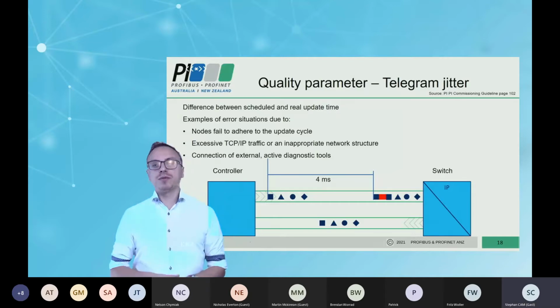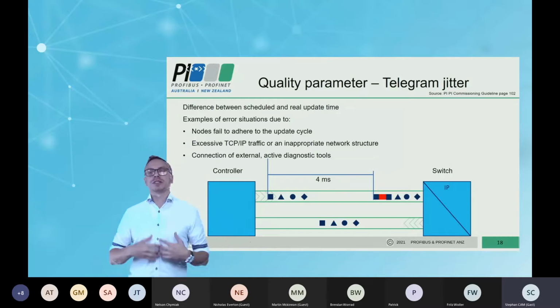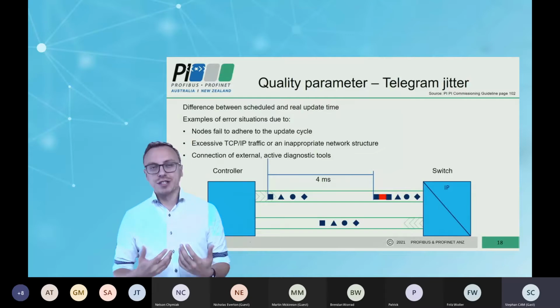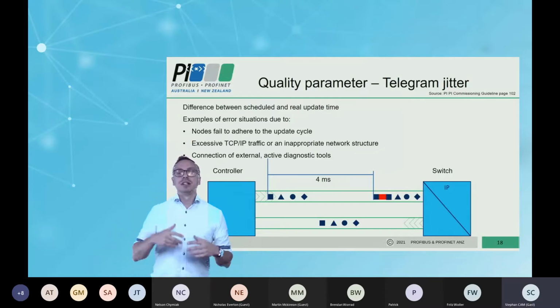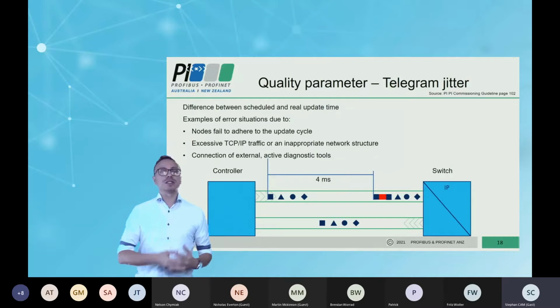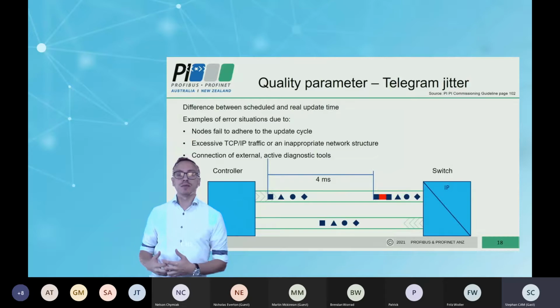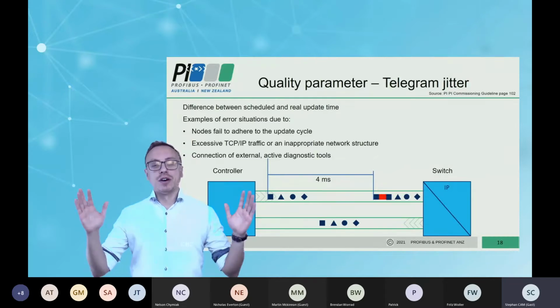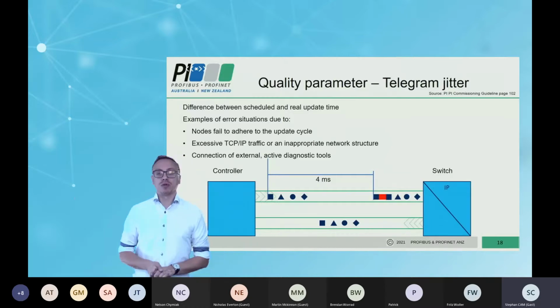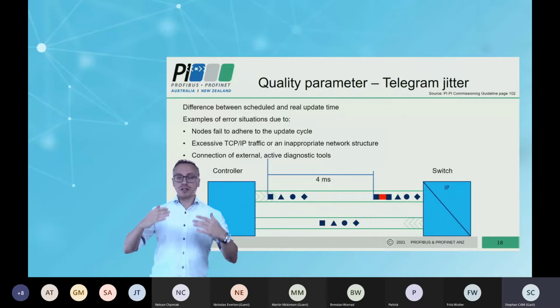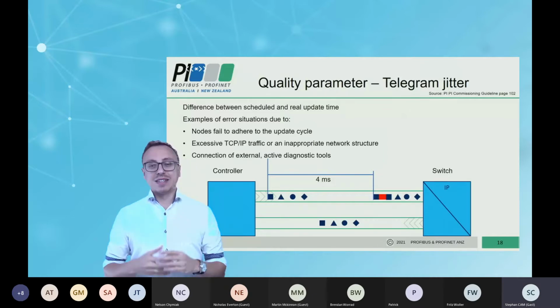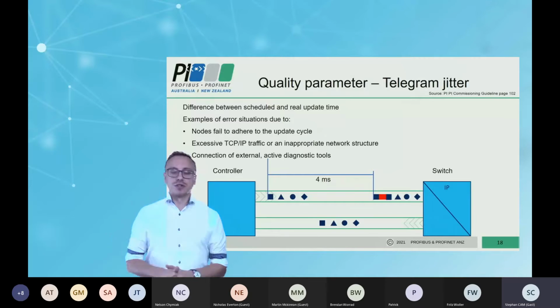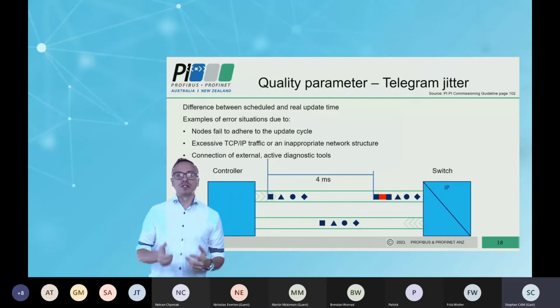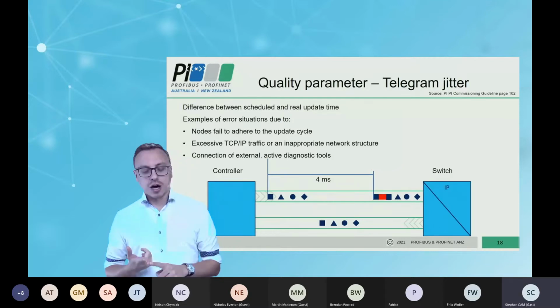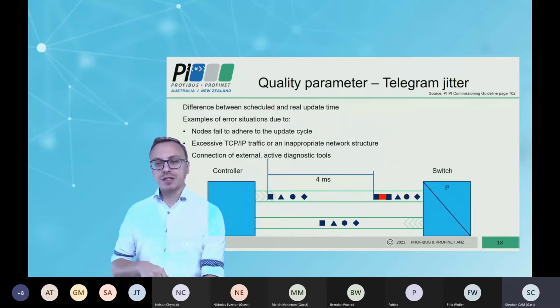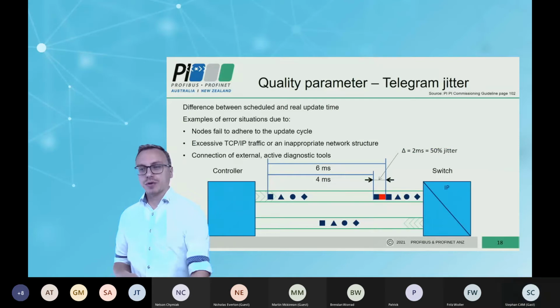For example, if you have old devices, so your devices or your network are aged, the jitter will increase. Or, for example, if you have additional TCP/IP transmission, each device has to check each frame. TCP/IP frames are normally very large, and this means the devices need more time, so your normal cyclical frames will come later, and this is why you get jitter. So jitter is a very nice quality value. With jitter you can find out if your system is aged, or how accurately your frames reach the PLC or the nodes. So a very important value.